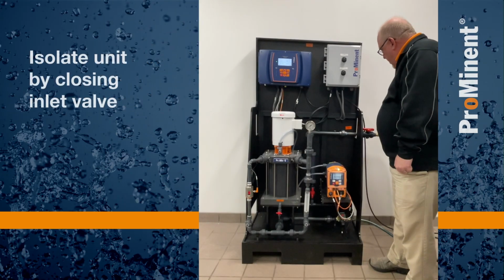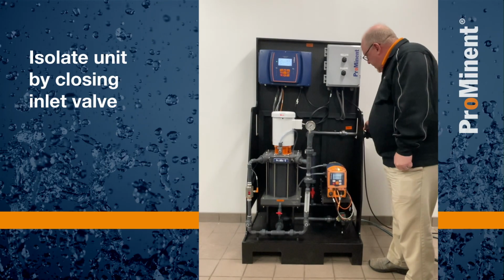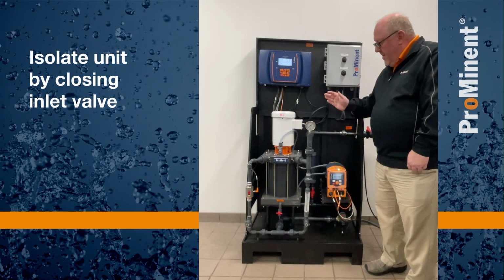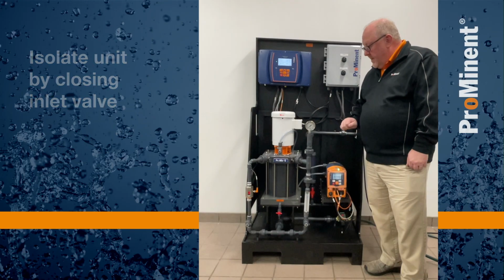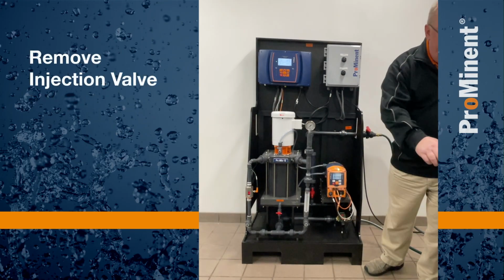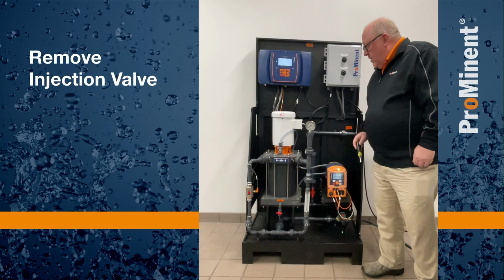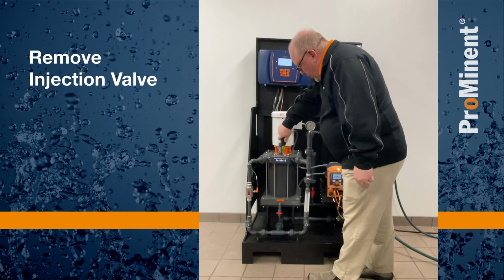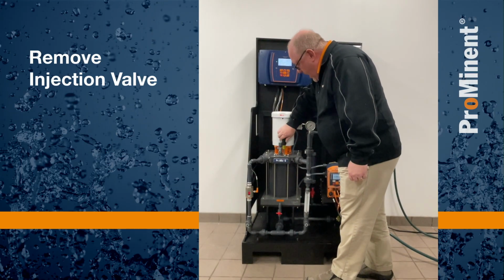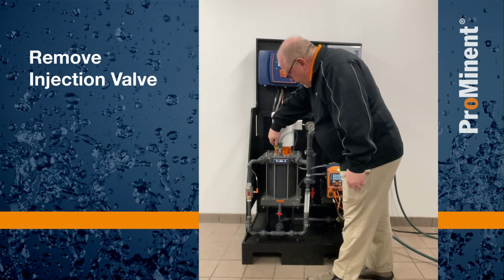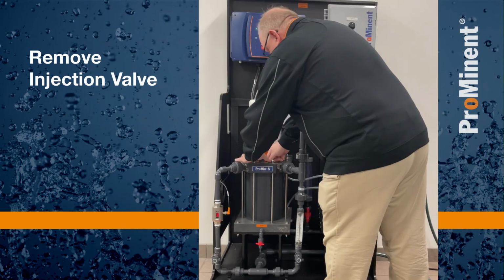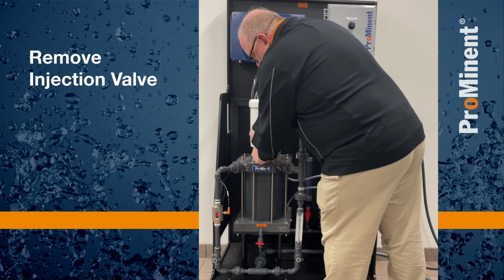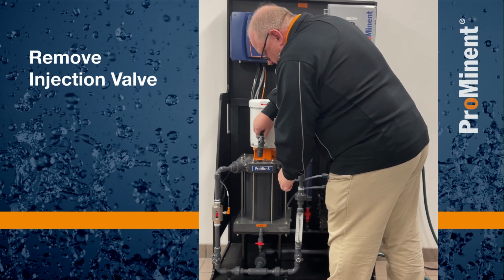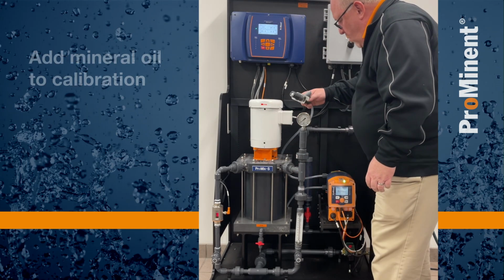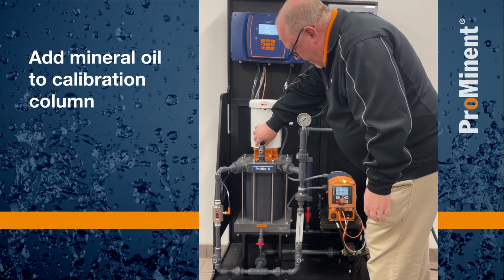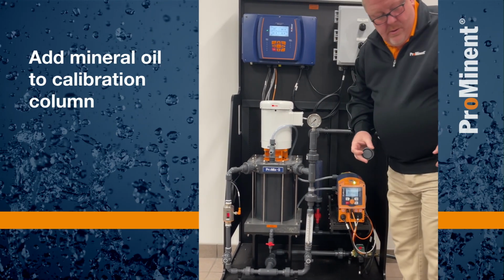Now what we would like to do is we're going to isolate the unit. So we're going to close a ball valve. That way we have nothing feeding back through the unit at this time. We're going to have to remove the injection valve. So to remove the injection valve, we have our quarter turn plate. We just need to loosen our two screws. Once we do that, we can quarter turn that plate and simply pull up on that and it will come out for us. What we're going to do is we're going to pump some mineral oil through that.